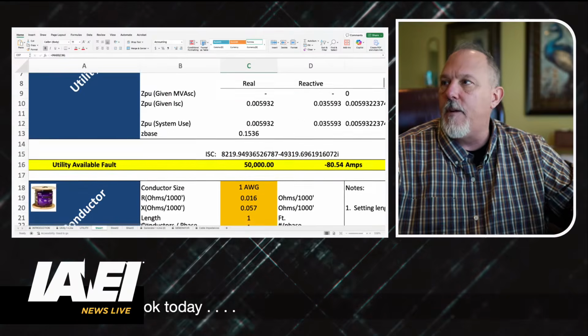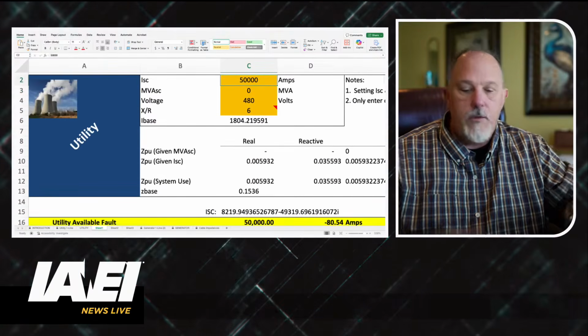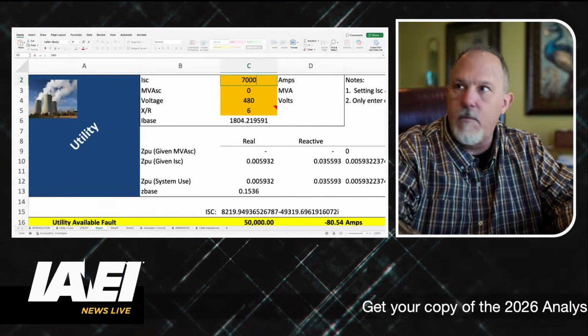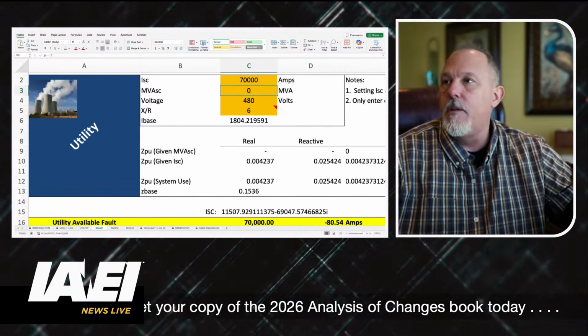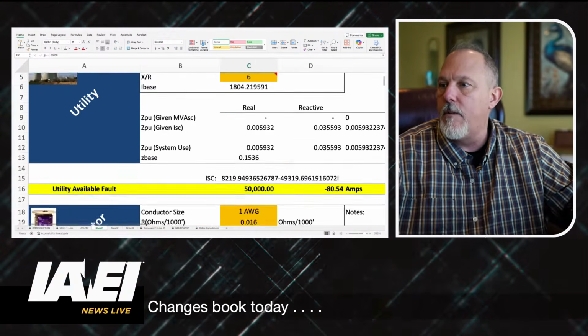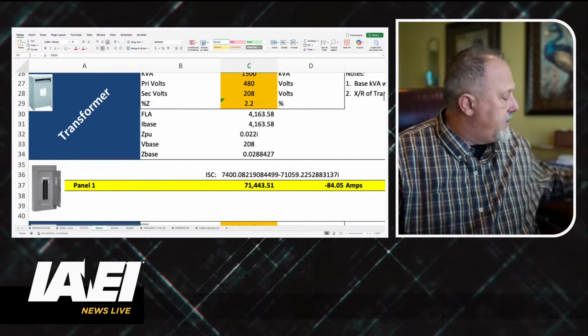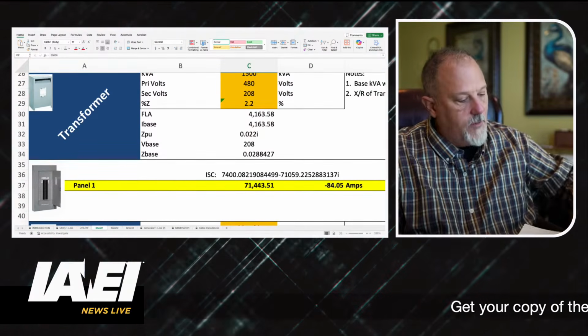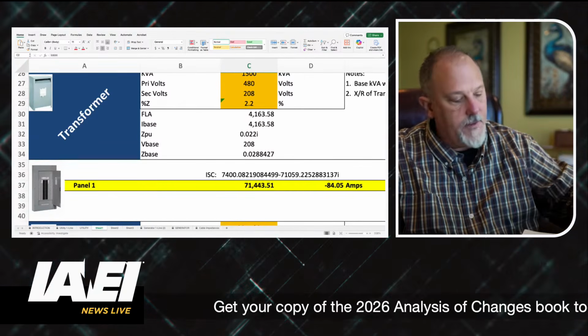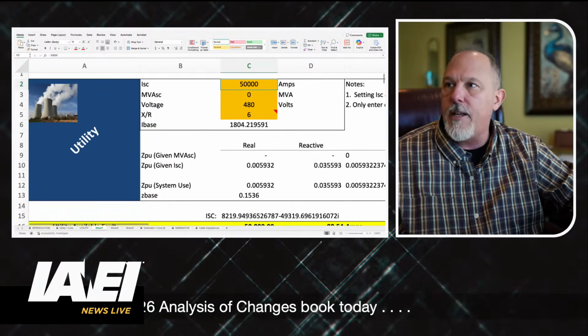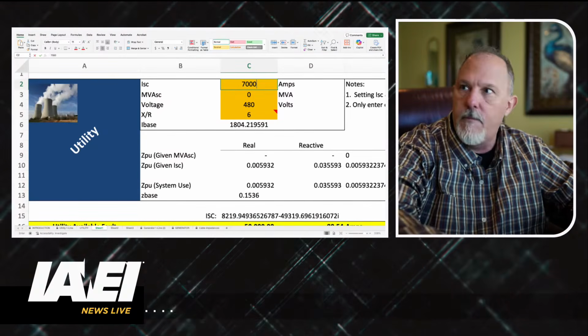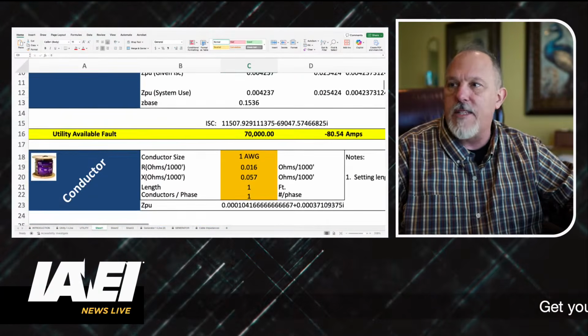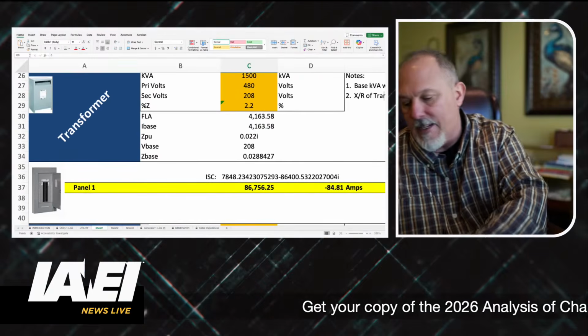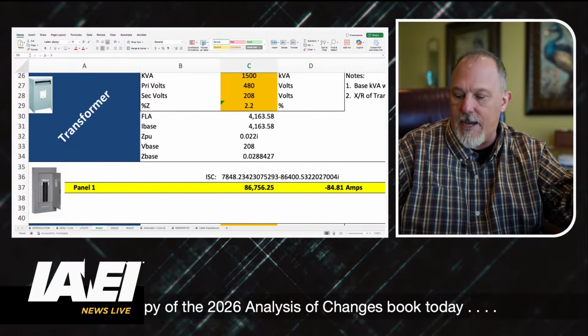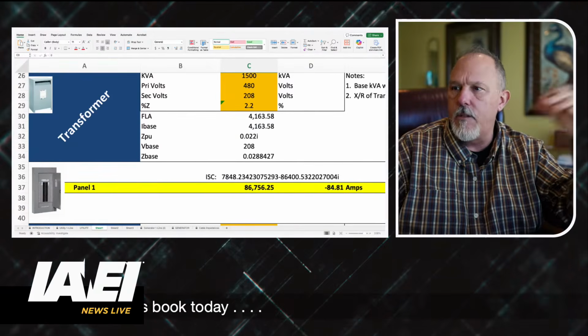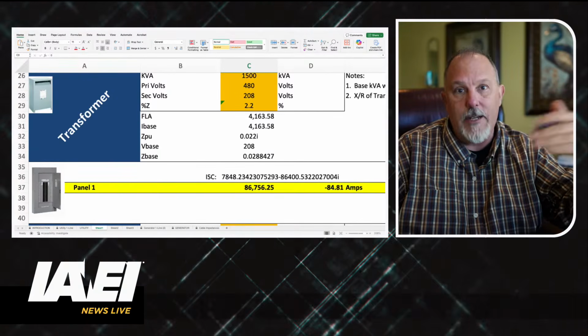Now let's change the primary from 50,000 to 70,000. So now my fault current went up 20,000. Well, let's go back. What was this number? 71,000. I've got to write it down. I got 71,000 amps, 71K, on the secondary. I come up to the top and change this to 70,000 amps, and I come down, there's my 70,000. And now I've gone to 86,000. So I went up 20,000 on the primary, and now I've gone from 71 to 86.